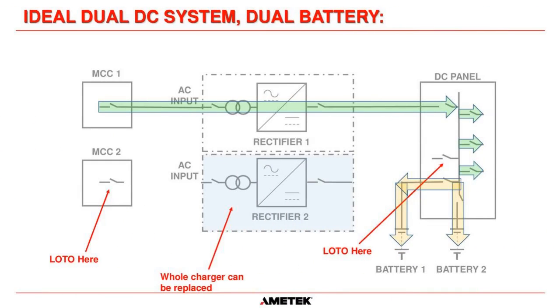So here's the advantage of parallel systems. I mentioned it earlier, but what you can do is replace a whole charger without affecting your load circuits. As you can see here, we have LOTOed MCC2. We have LOTOed this breaker here. So we have no power at these terminals. We have no power at these terminals. Those wires can be disconnected, and we can take rectifier 2, completely physically remove it, and then install a brand new charger, power it up, test it.